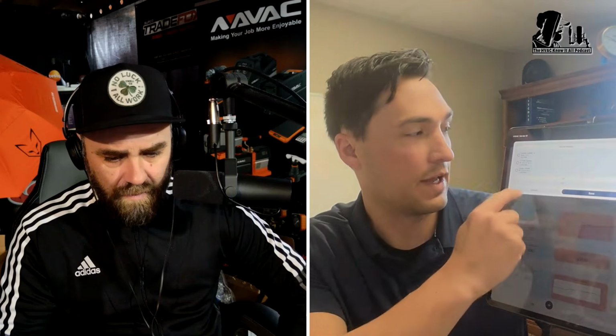So in here, you can go to your system settings and you can input a volume of CFM, or you can use your hot wire anemometer to give you an actual real world measurement of your CFM. Either one. So that's what I wanted to hear, because a lot of people will say, okay, yeah, the system is designed for this, and they'll plug in that number, but it might not be the actual CFM that it's outputting. So it's best to have the actual reading plugged into the app rather than just a guess.